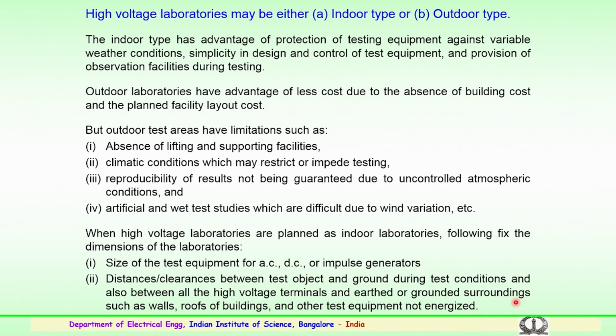The clearances are very important: the distances between the test object and the ground during test conditions, and also between the high voltage terminals and the earth or grounded surroundings. It could be metallic structures nearby, grounded surroundings like walls or roof of a building, or other test equipment which may not be energized. So, these points have to be considered when high voltage laboratories are being planned as indoor laboratories.